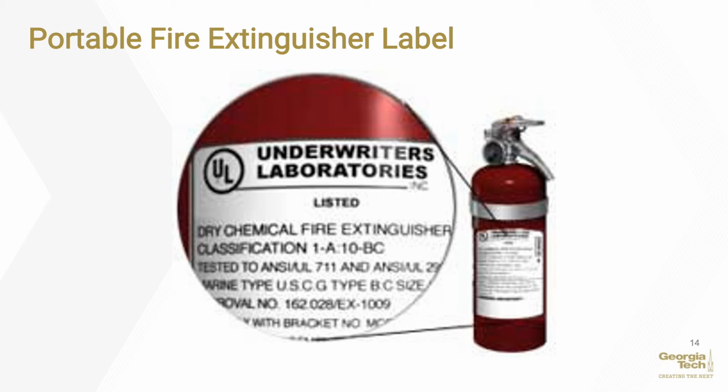The number in front of the B rating represents the area in square feet of a Class B fire that a non-expert user should be able to extinguish. Using the above example, a non-expert user should be able to put out a flammable liquid fire that is as large as 10 square feet.